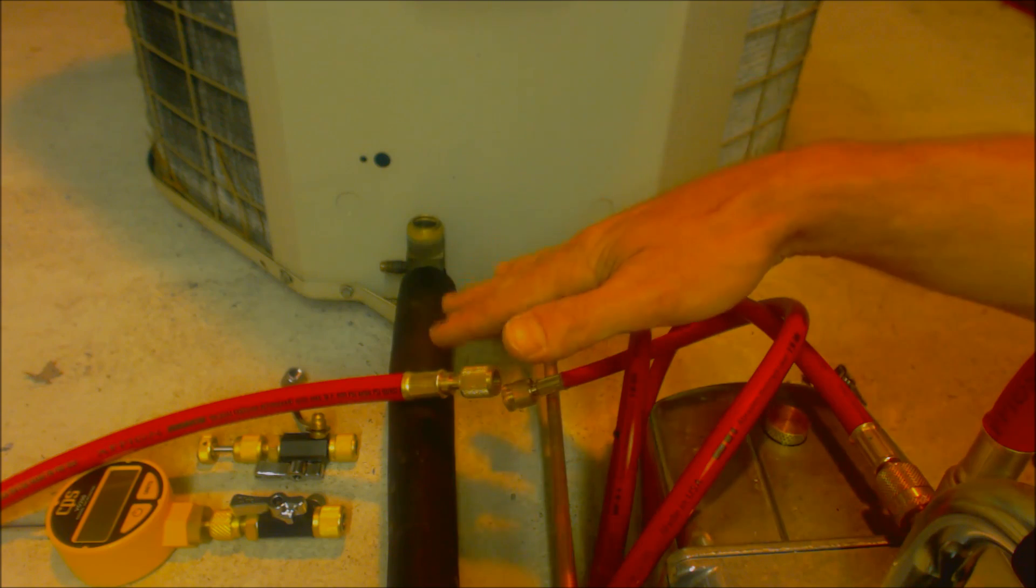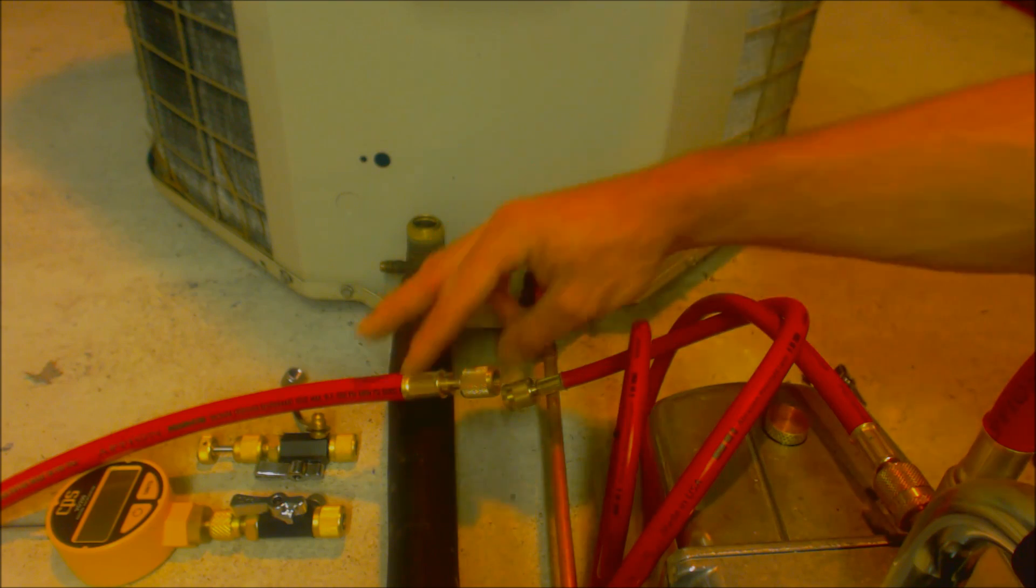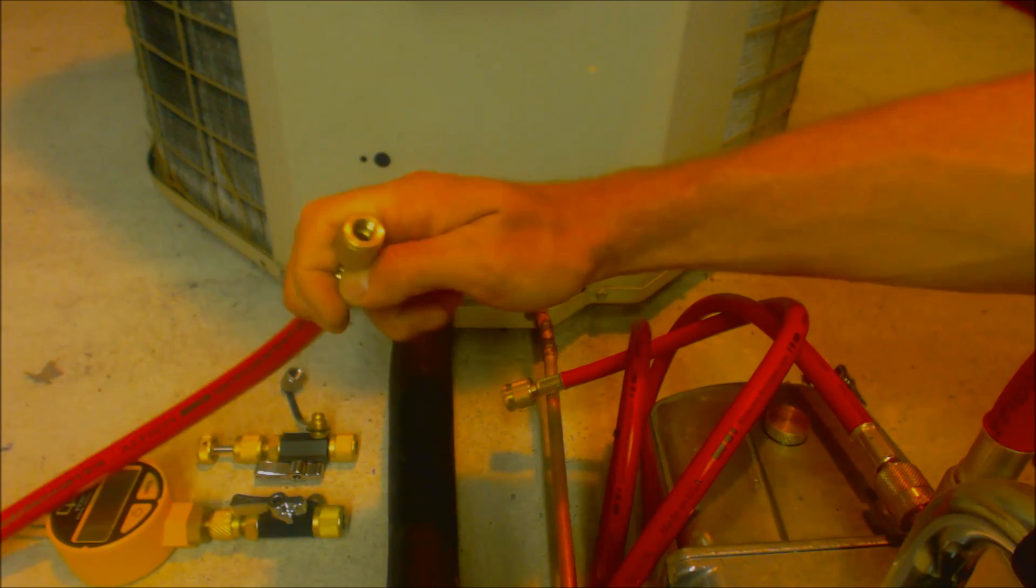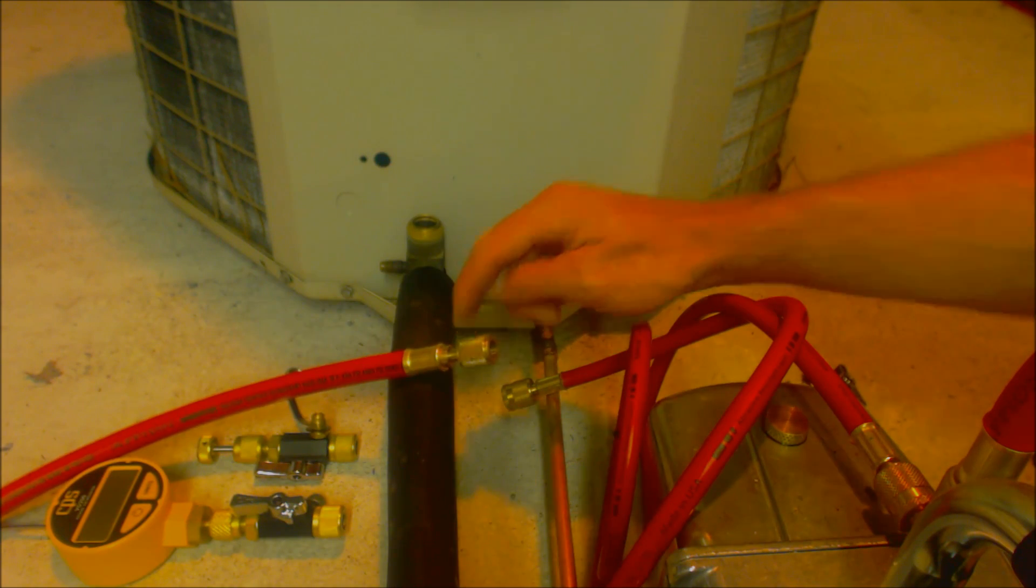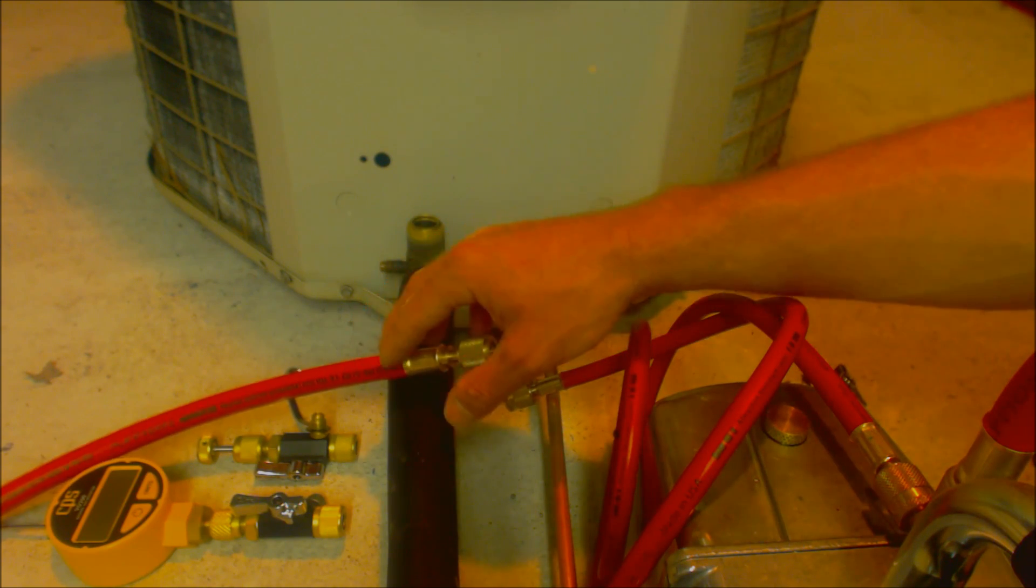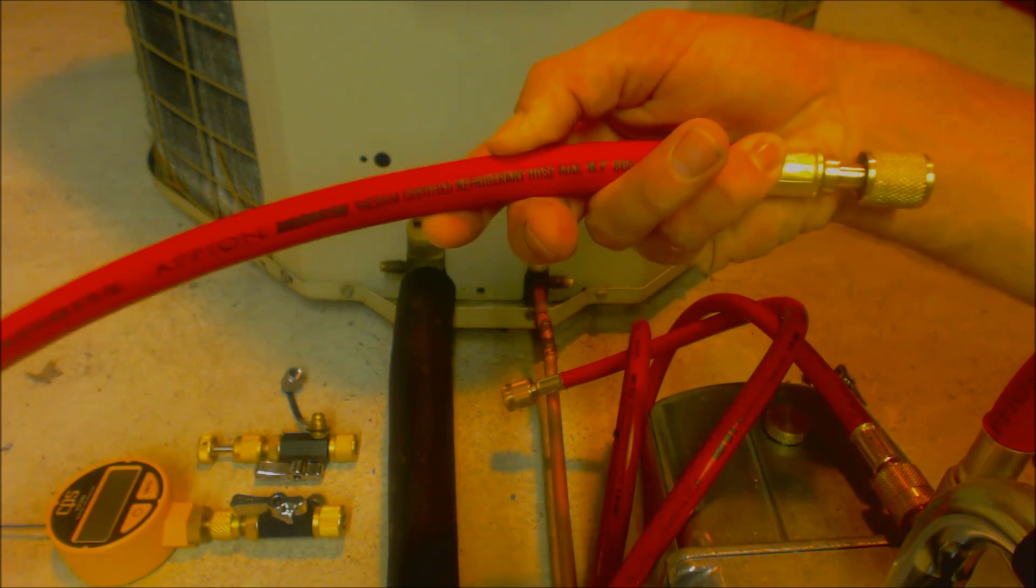The reason that we're not using a manifold gauge set is you have more potential for leaks, and I know in the past that's driven me a little crazy at times trying to find the one hose that might be leaking. You want to make sure that you have vacuum hoses that are rated for vacuuming. They're built a little differently than the normal service hoses that are rated for just pressure. These are actually for vacuum and it says vacuum certified on the refrigerant hose.